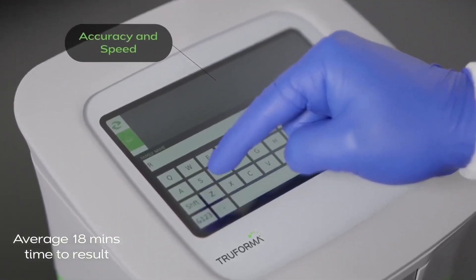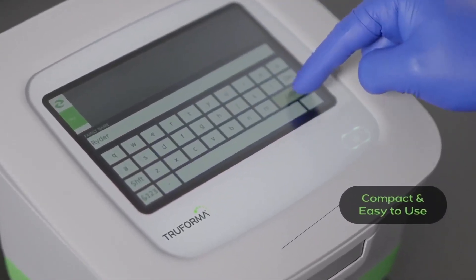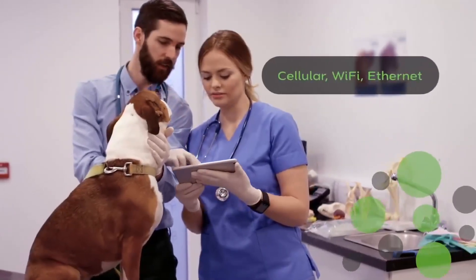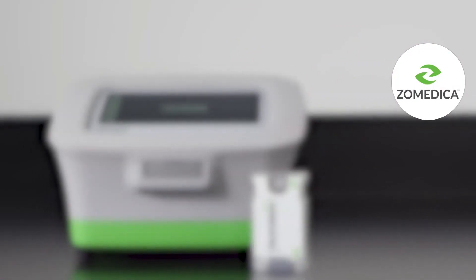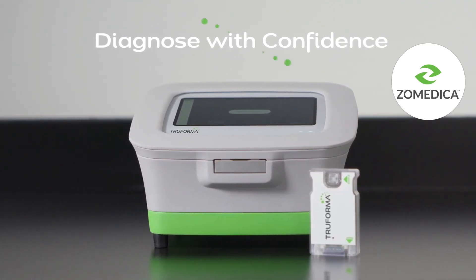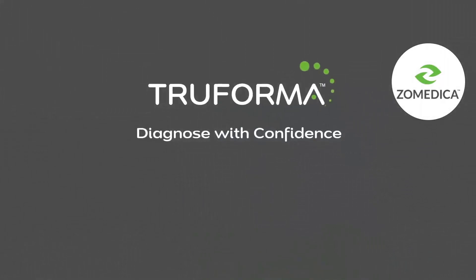Because the BAW sensor operates at high frequencies, it has a very low limit of detection — measuring changes down to 10 picograms per milliliter. The platform initially targets assays to detect thyroid and adrenal disorders in dogs and cats, with new assays anticipated including gastrointestinal, diabetes, renal, and infectious disease testing. All tests use a reference analysis eliminating background effects such as temperature, viscosity, and non-specific binding. The semiconductor design makes the platform multiplex-capable, allowing several tests on the same sample — all completed in an average of 18 minutes. For more information, visit zomedica.com.